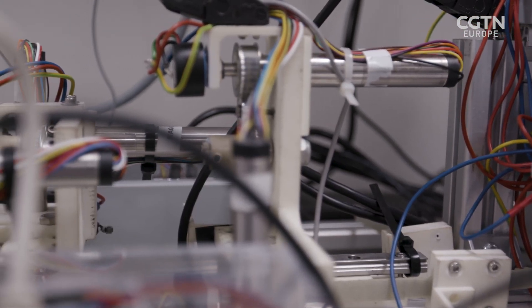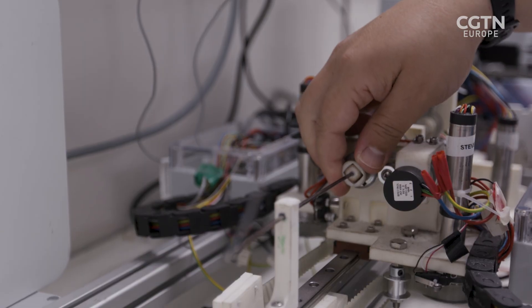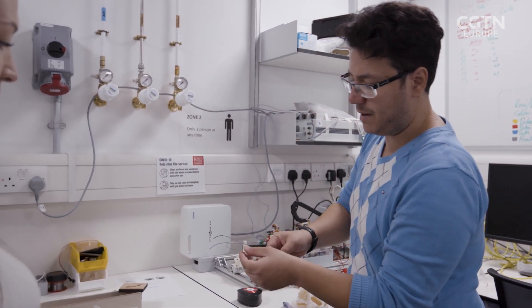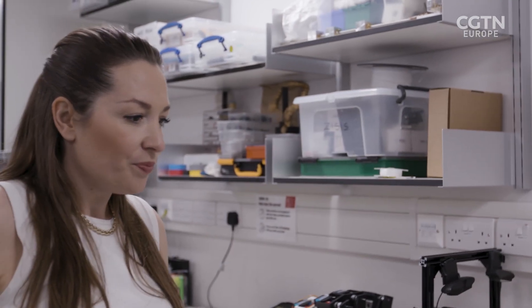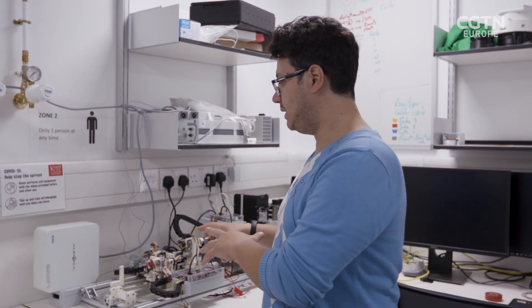This is a big-scale system demonstrating what's called concentric tube technology — flexible robots that move like an elephant trunk. The end effector at the front is the part that would go into the eye. While this demonstration model is large, the team is making tiny instruments around half a millimeter to one millimeter in size. The goal is to create a microscale human hand inside the eye, with algorithms designed to maximize the angular dexterity of the tip, enabling wristed-like motion — going in tangentially, at a specific angle, or grabbing and lifting tissue.